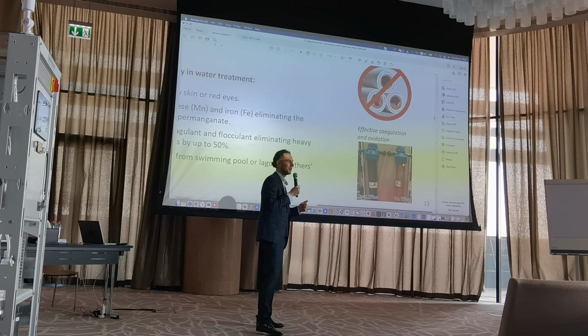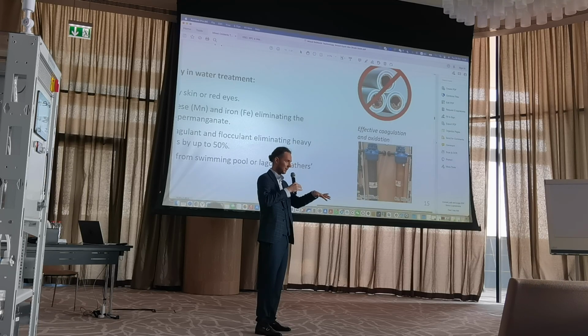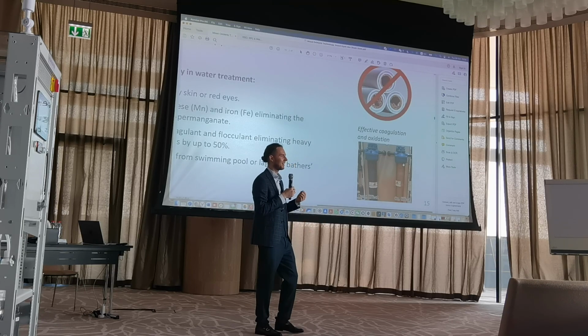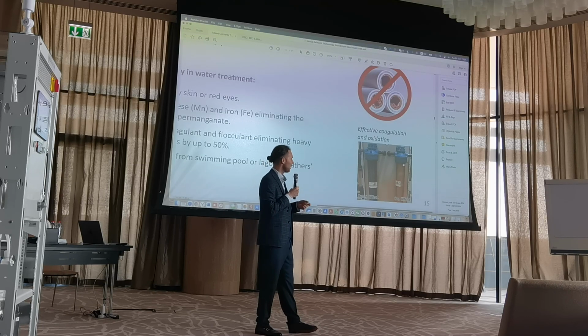Same in the swimming pool. We start dosing coagulant before the filtration system, because a lot of what's called biological effluvia, or biological things, gets into the water from our bodies when we swim, and these are very difficult to filter. Sand filters cannot keep it, but with the addition of coagulant, it starts to coagulate and you can filter it out.